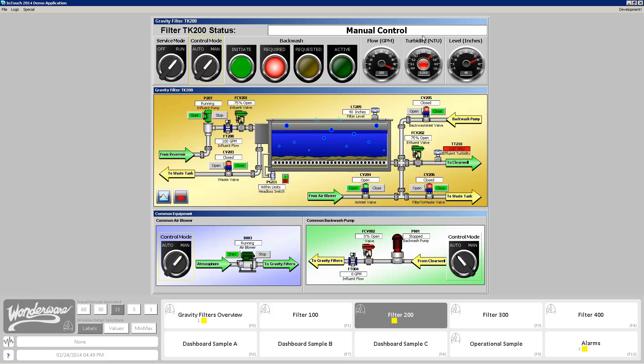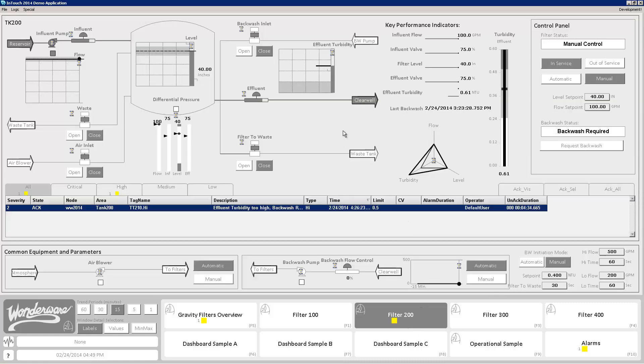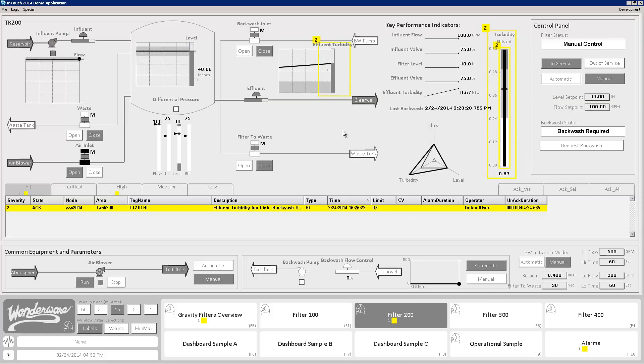So those were examples of bad color use. Now let's look at better practices. I took this same graphic and recreated it utilizing situational awareness focused techniques. In this case, you'll see the colors are mostly focused on a gray palette when there's nothing to be acted on, and yellow is clearly indicating where action is required. This allows you to utilize color contrast to guide the operator's attention.